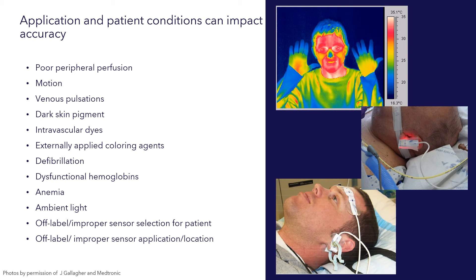Dark skin pigmentation, because of melanin, which readily absorbs the infrared and red light, may overestimate the oxygen saturation of patients with darker skin. Certain intravascular dyes that are injected as part of diagnostic procedures, such as methylene blue, can also create errors within oxygen saturation measurements, as well as externally applied coloring agents or nail polish, especially of the darker variety.